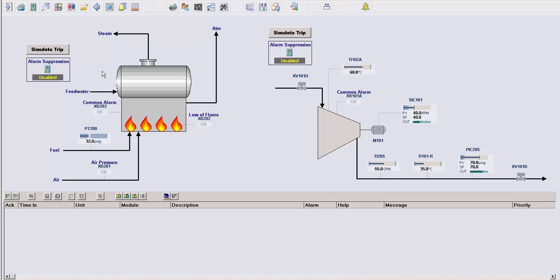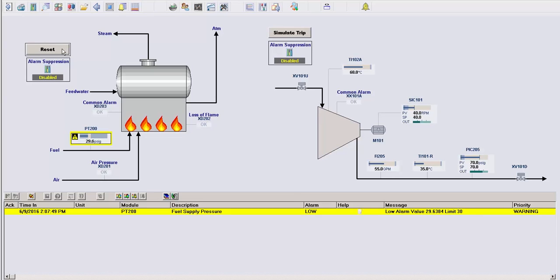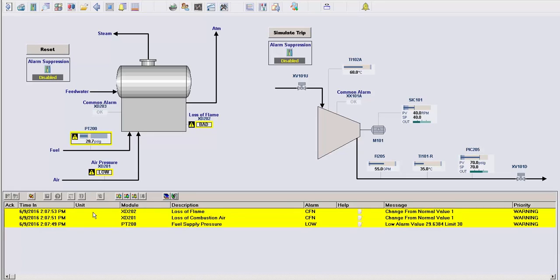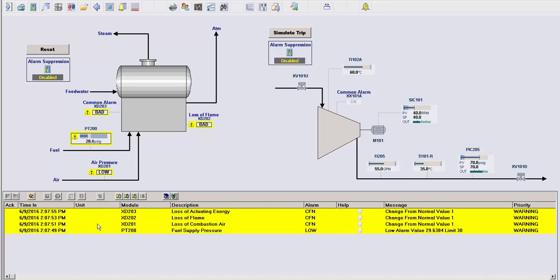I'm going to simulate a trip of this boiler on low fuel pressure. And we can see that because of this boiler trip, we now have multiple alarms showing up on our banner for not only the low pressure, but the air pressure, loss of flame, and common alarms as well. All of these alarms for what is essentially a single event.